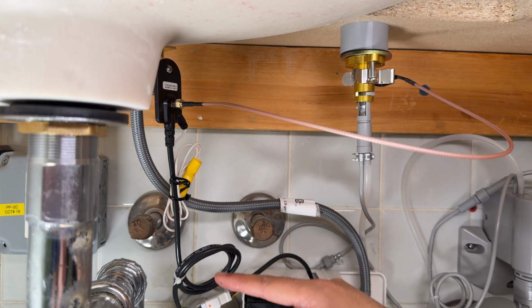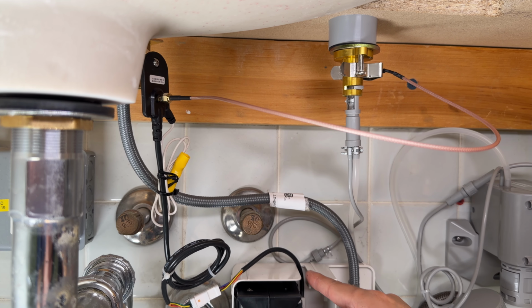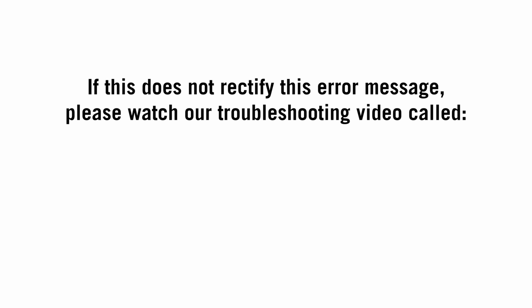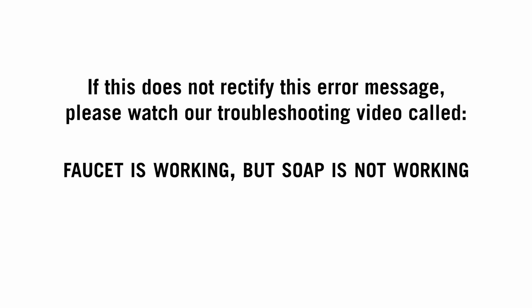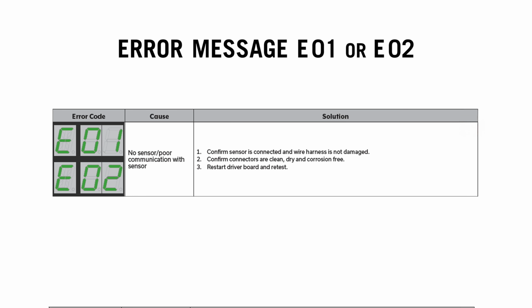Be sure to route the sensor cable away from power supply wires of any type. If none of this helps rectify this error message, please watch our troubleshooting video called Faucet is working, but soap is not working. Next, if you encounter message E01 or E02, it means that there's no sensor or poor communication with the sensor.